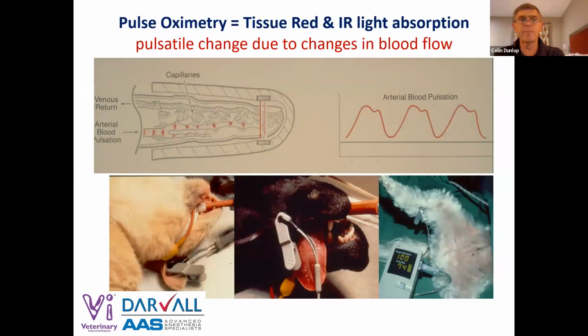Well, they're pretty clever. If we put that pulse oximeter on our finger, it transmits red and infrared light through our finger. As the pulse travels through the finger, the amount of light changes, so the machine can generate a pulse. But the first thing the machine has to do is figure out how much of that light is absorbed by the tissue. So if you look at the graph on the right, there's an area from the baseline up. That's what we call the background light absorption. And then the machine figures out the pulse, and it picks the pulsations up. And then from the red and infrared light and the peak of the pulsations, it determines the saturation value.